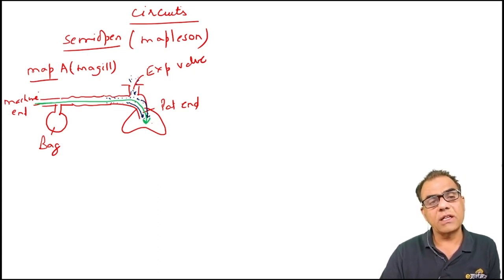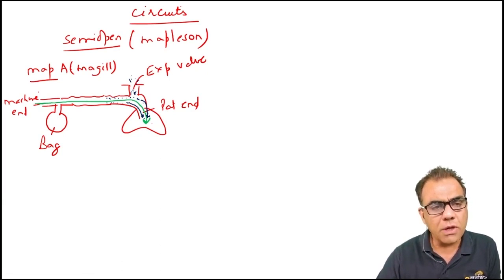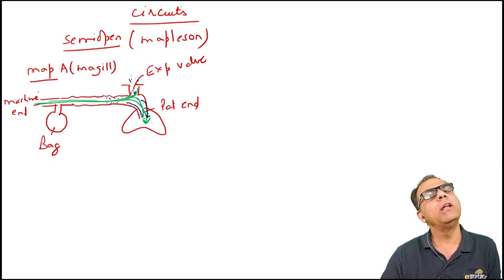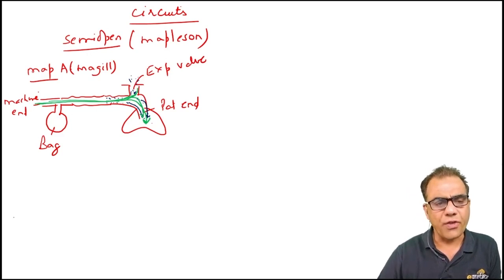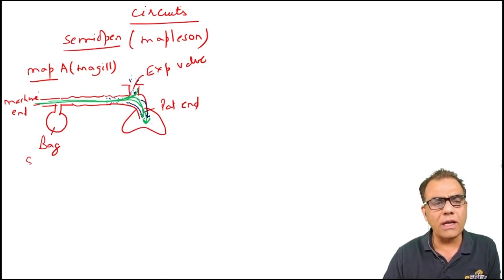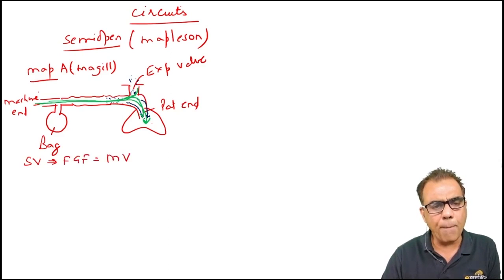But the aim of every circuit is that there should not be any rebreathing. And how to prevent this rebreathing? The fresh gases coming from the anesthesia machine should be sufficient, first to push these expiratory gases out of this expiratory valve and then to be delivered to the patient. So the fresh gas recommendation for Magill circuit is that if you are using it for a spontaneously breathing patient, spontaneous ventilation, then the fresh gas flow requirement should be equal to the minute volume of the patient. Means fresh gases coming from the anesthesia machine should be equal to the minute volume of the patient.